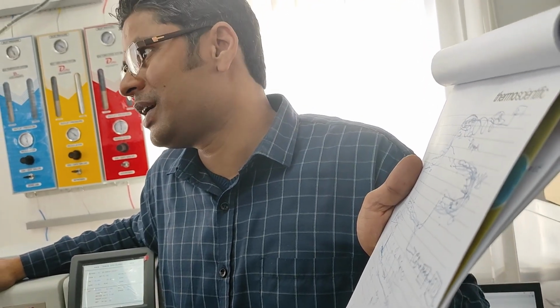Why did I say delete the peak? It's unwanted. You cannot report twice for a single component, right? You have to report only one. But it is possible that you get two peaks in different detectors for the same component, because it is detected in TCD at percentage level, and as it is converted into methane, it is now detected in FID.